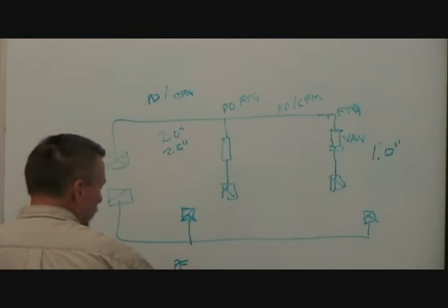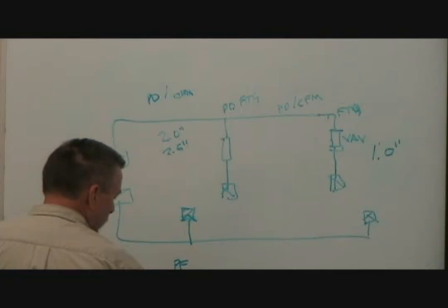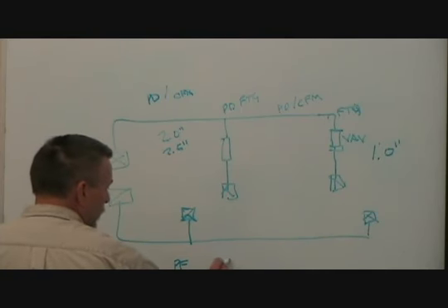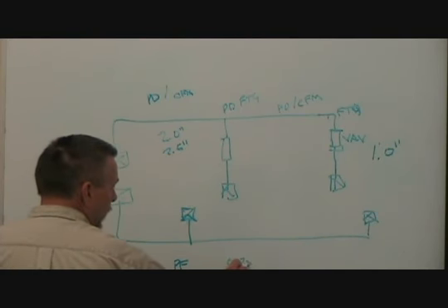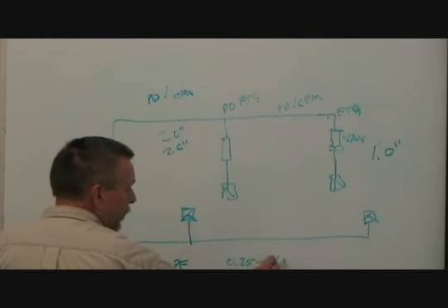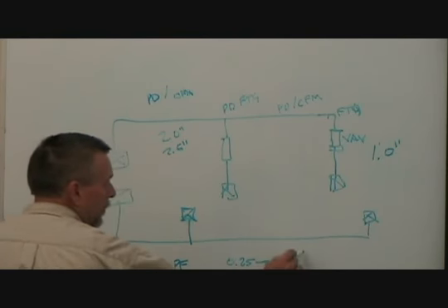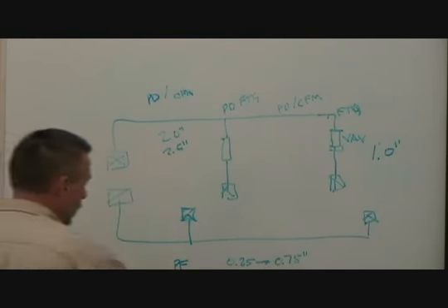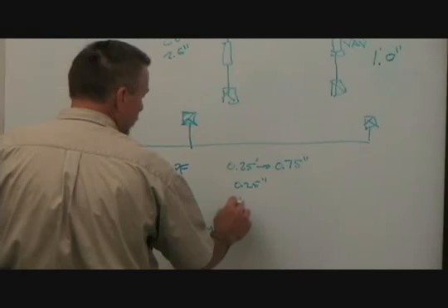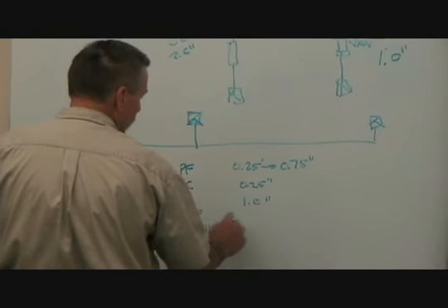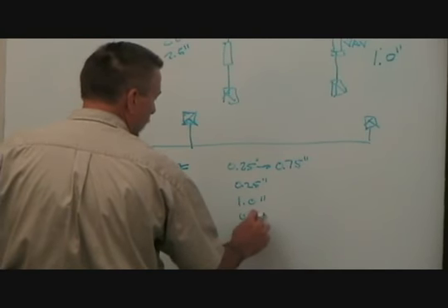So pre-filter, and then you might have a final filter. Pre-filter generally is going to be in the range of 1/4 of an inch, but you want to figure it dirty. So you might figure it at 0.75 of an inch. And a preheat coil, generally about 1/4 of an inch for a 2-row coil. A cooling coil is generally about 1 inch. Diffuser, about 1/4 of an inch.